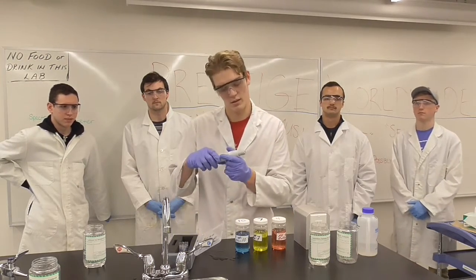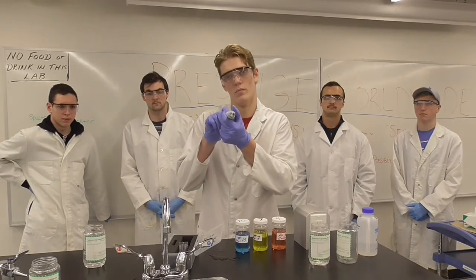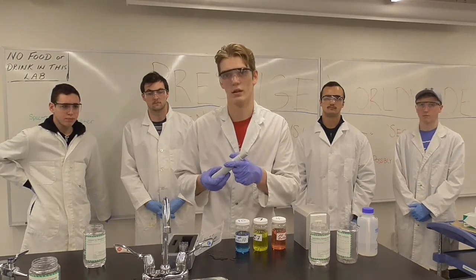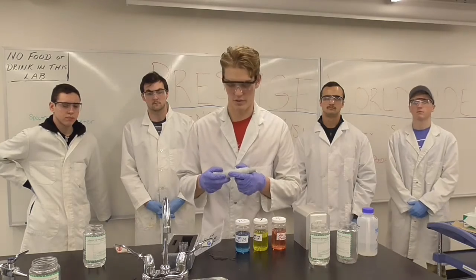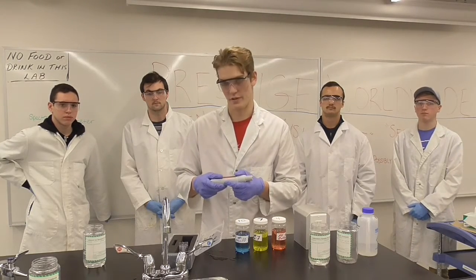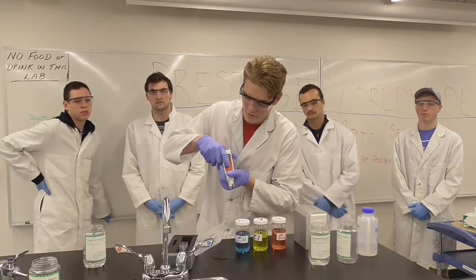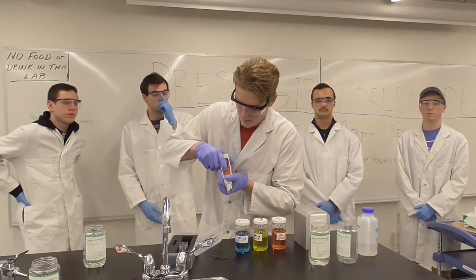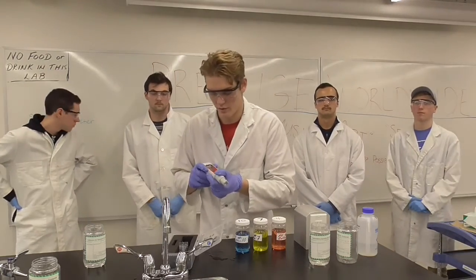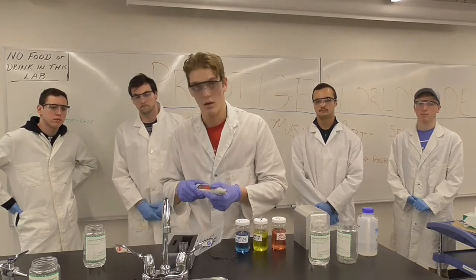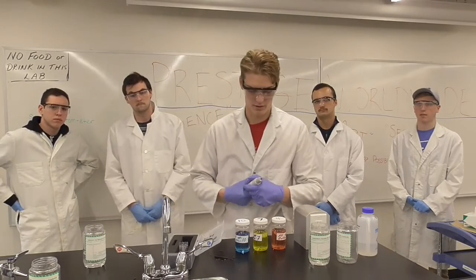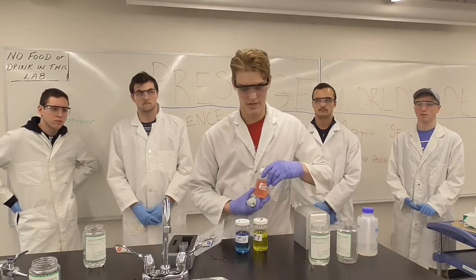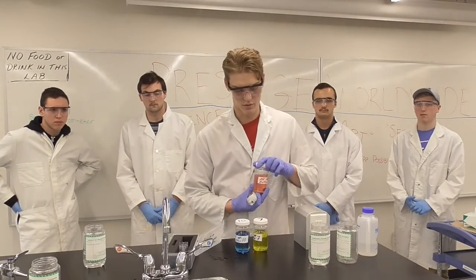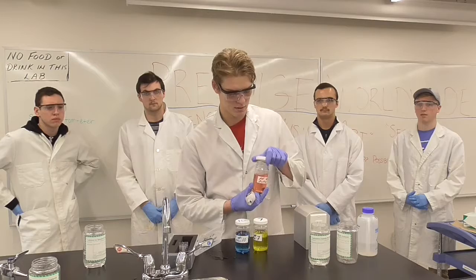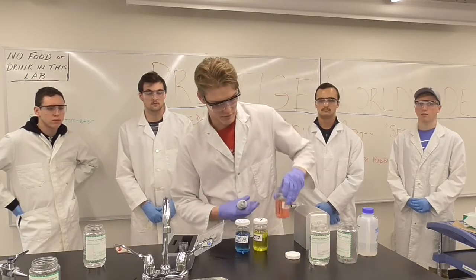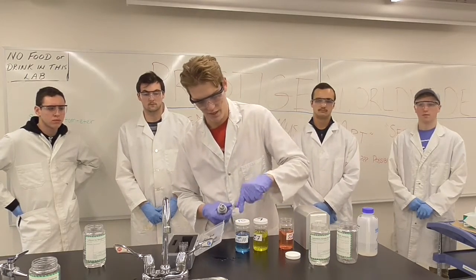And then the next thing is to make sure that this probe is not scratched or damaged in any way, because that will affect your pH reading. So your next step is to turn the pH meter on, which is this button right here. You just need to press it and hold it and give it a couple seconds and it'll turn on. So we're going to calibrate it to start. To calibrate it, you need 3 pre-made samples that already have a known pH of 4, 7, and 10, which we have just right here. This is my 4, 7, and 10.